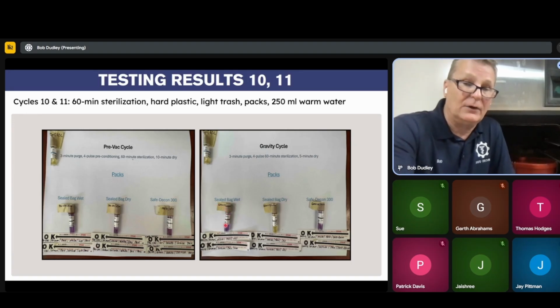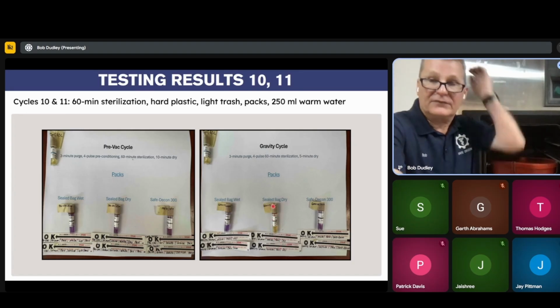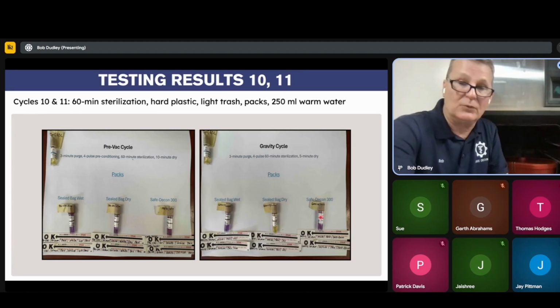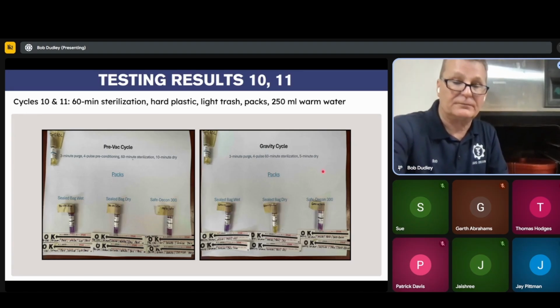The wet bag on this one did rupture, and we were able to get the sealed wet bag. It did okay. The dry bag stayed shut, it didn't bust. It still had the little half-inch hole at the top that was in there. You can see that the indicator said that there was good steam and heat. Failed BI, did not work. And the Safe-Decon one, we got the kill. Again, these were just on loose packs, not the hard ones.